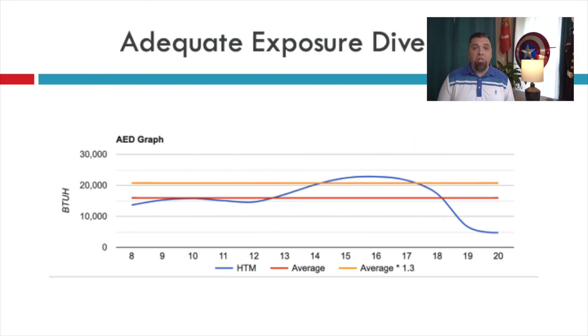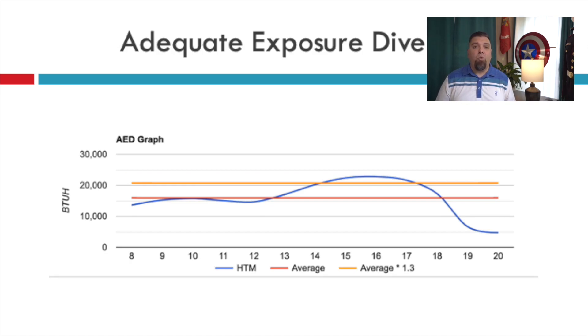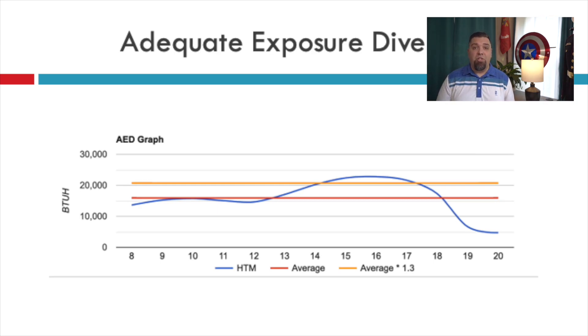There can be multiple peaks. As you can see in this example, this is what you normally see with normal adequate exposure, but just a little bit more glass on the south or southwest portion of the house, because this peak goes above 130% once we reach 4 or 5 p.m. This is normal for the northeast. Keep in mind this could change when we talk about October cooling as well — this is for normal July cooling.